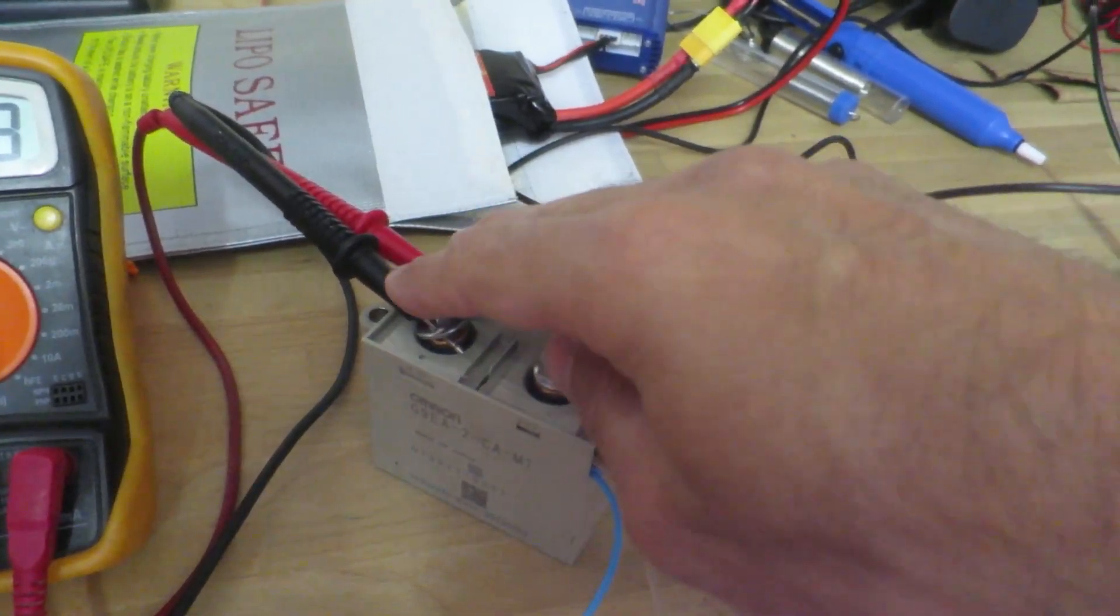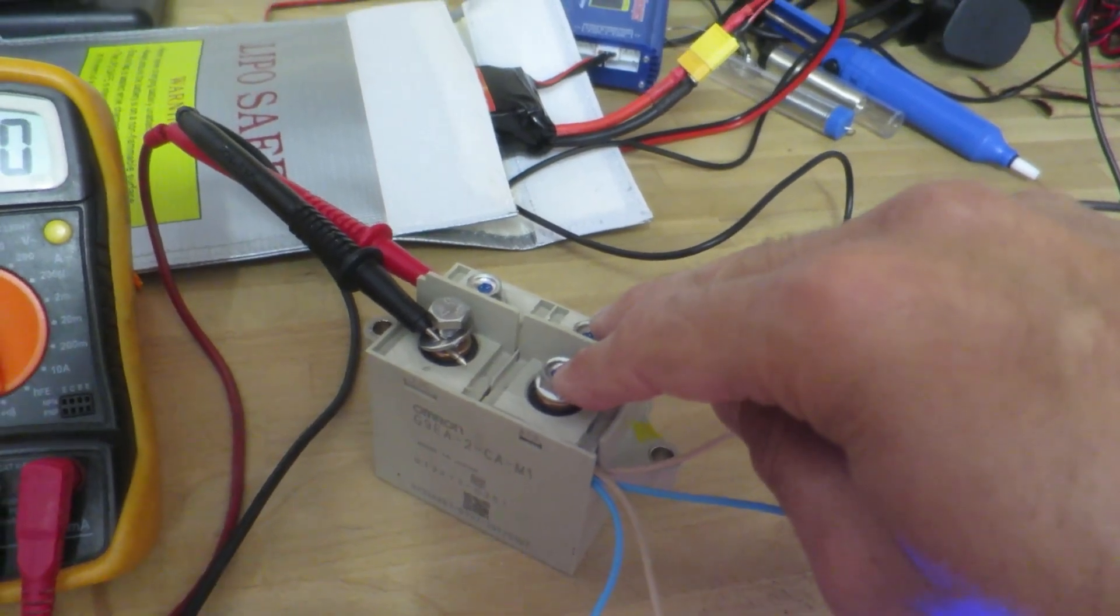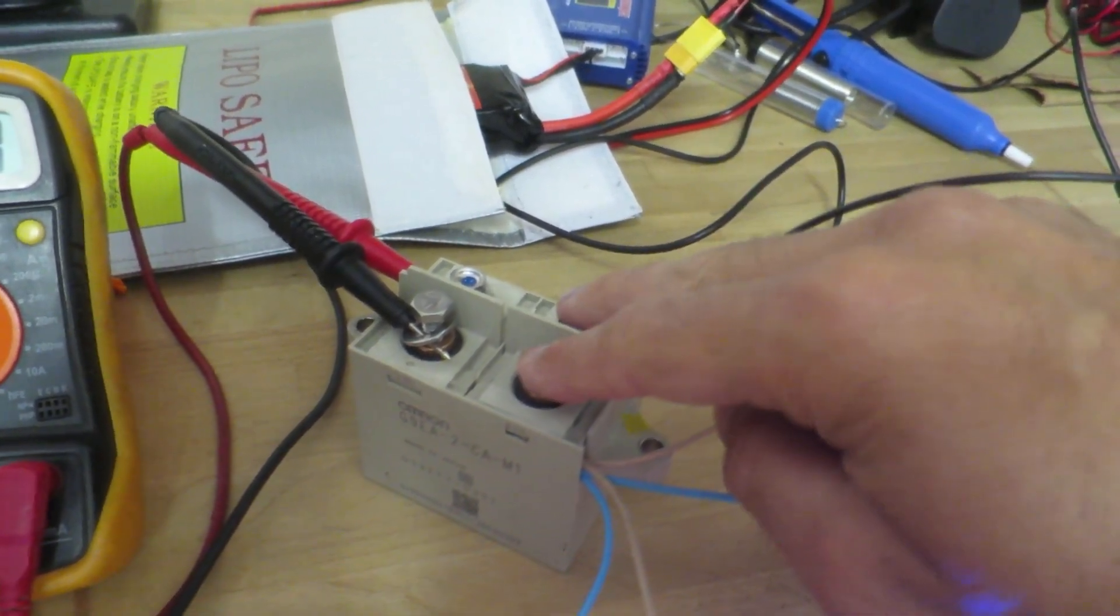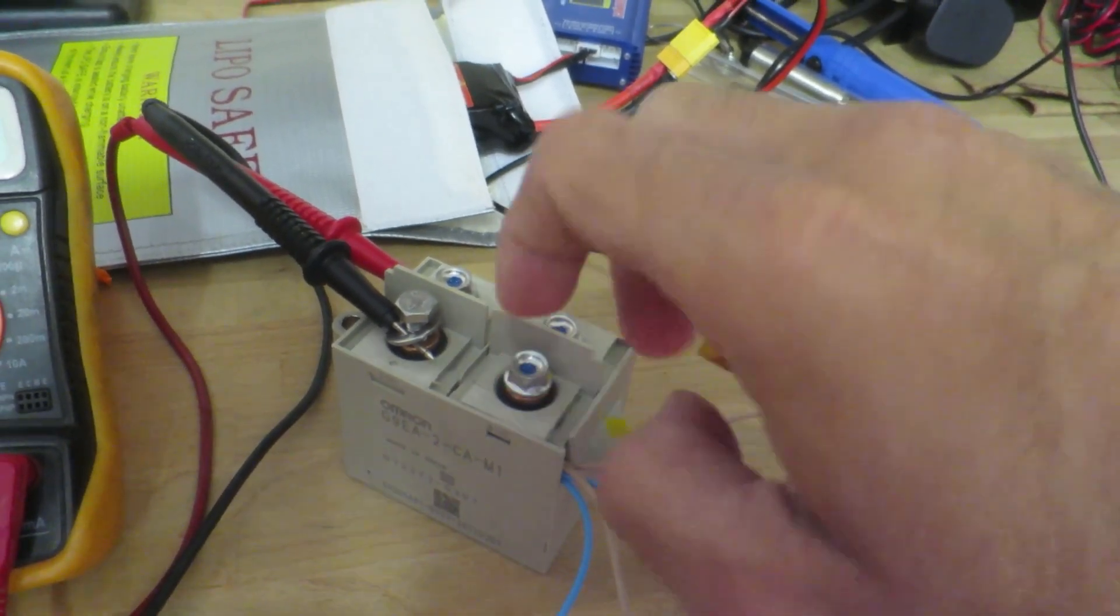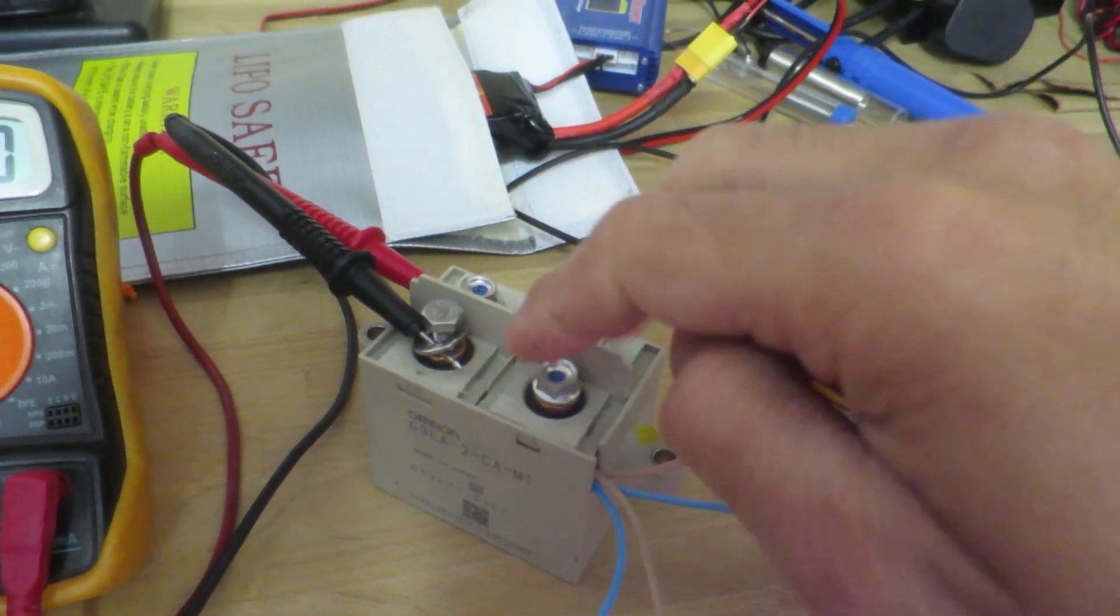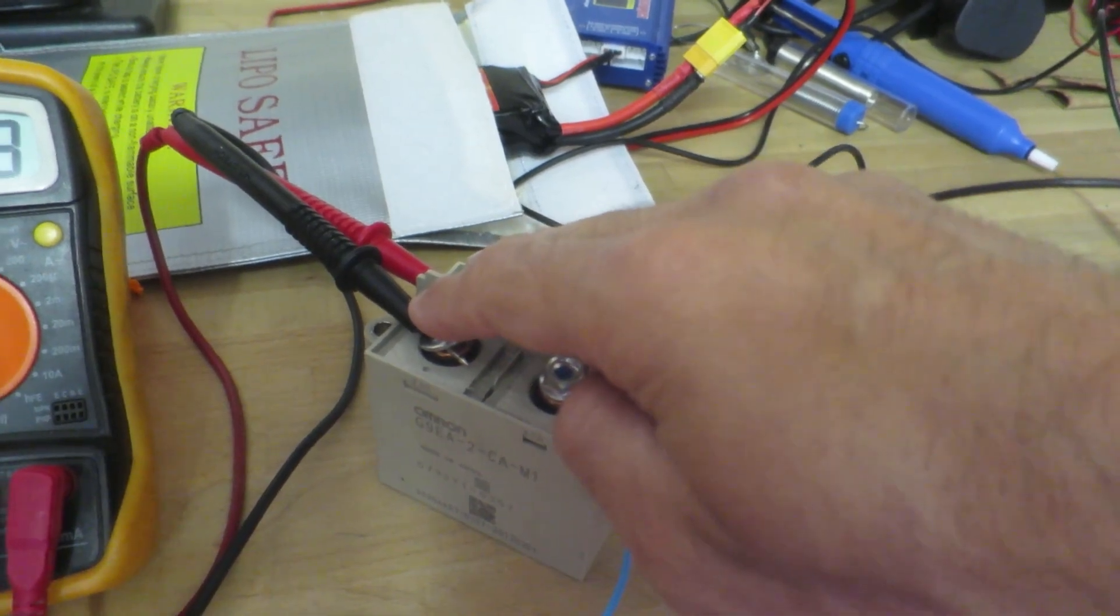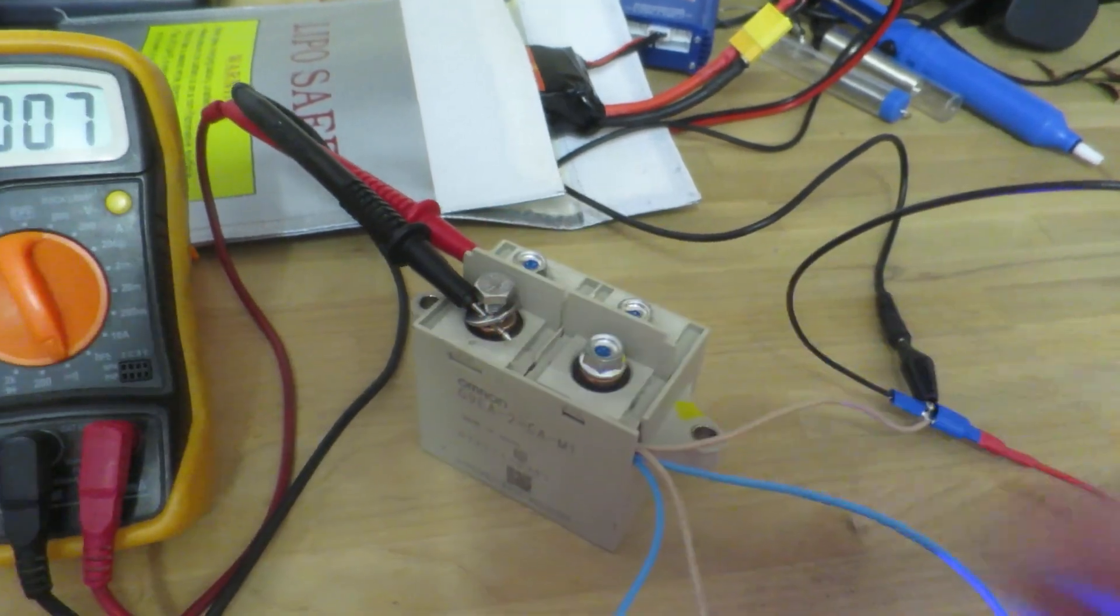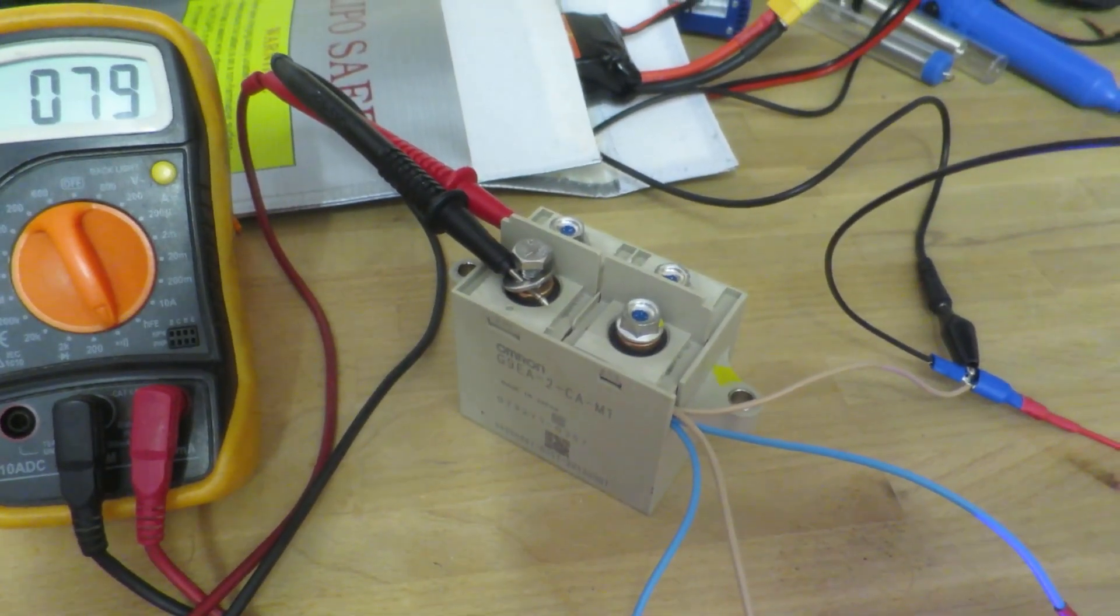So currently both of these are being driven but it doesn't matter because this circuit here, the pre-charge circuit, will be ignored because there's a high resistance in the way. All the power will flow through here and your pre-charging is done and fingers crossed that will stop my contactors from being damaged in the future.